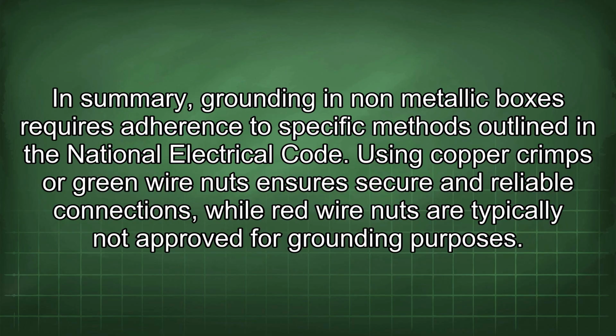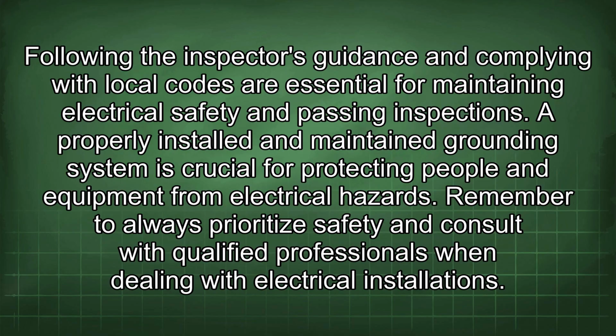In summary, grounding in non-metallic boxes requires adherence to specific methods outlined in the National Electrical Code. Using copper crimps or green wire nuts ensures secure and reliable connections, while red wire nuts are typically not approved for grounding purposes. Following the inspector's guidance and complying with local codes are essential for maintaining electrical safety and passing the inspections. A properly installed and maintained grounding system is crucial for protecting people and equipment from electrical hazards.